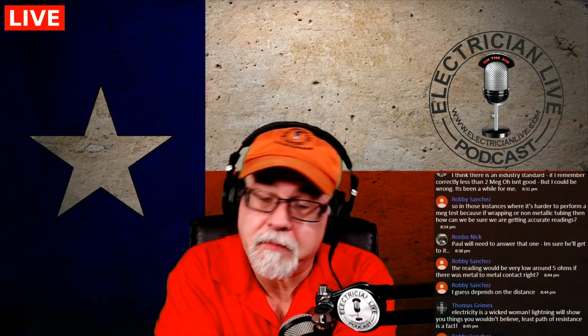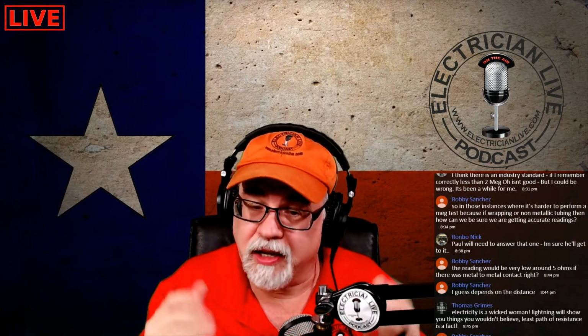All right, it doesn't mean there's no place for MEG testing, because there is, and I gave you the reasons why. Medium voltage is beautiful. High voltage, it's beautiful. Motors, transformers, anything where you have a dielectric separation between ungrounded and grounded parts, then it can be beneficial in equipment, okay? But when it comes to the validity of insulation on a conductor, which can be pretty darn thick in mils, it's pretty tough if you don't have a return path, okay?